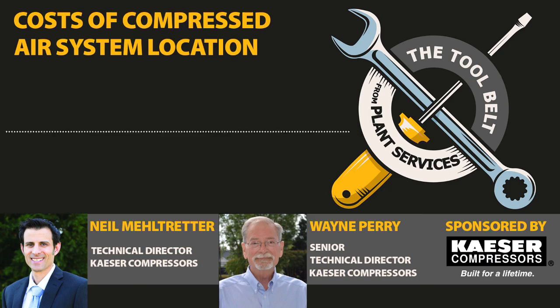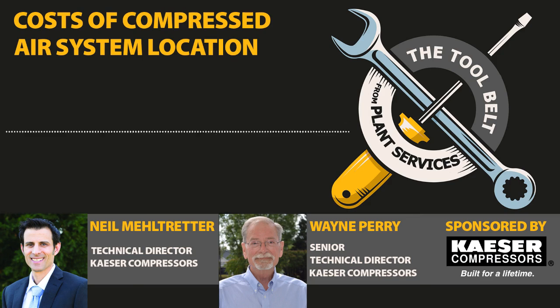That's just from a servicing point of view. The other aspect of having good clearance around the compressor is that you generally get good airflow - if you have a lot of clearance, you're not blocking any paths. It's also safer for any service technician working in there, because they have room to move around and aren't cramped or squeezed into tight places. It's a real safety issue, and that's high on my priority list - making it safe for people to work around that equipment.